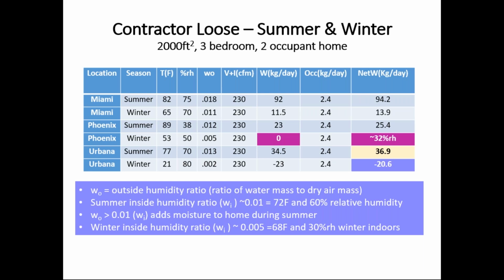Phoenix is lower in humidity during its humid season than Urbana. So instead of 36, 37 kilograms of water or liters of water per day that need to be pulled out in the summer, maybe as much as 25 under the same type of loadings as the Urbana house. When we look at the winter in Miami, as we mentioned, much lower but still needing dehumidification.